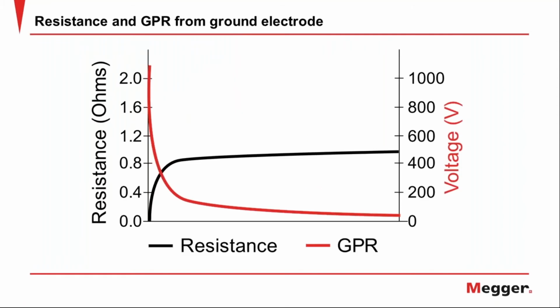And what that's doing, as we just see here, is guarding against ground potential rise, which can occur because the currents, which were previously spread out through an enormous amount of soil, as they approach the substation or the source, the grounded transformer, whatever it happens to be, then of course the field narrows down. Instead of spreading out, they have to channel down into the substation grid or whatever it's seeking as its return. And so that's where you get ground potential rise, and that can certainly be very dangerous, and you do want to make sure that you're guarded and protected against it.